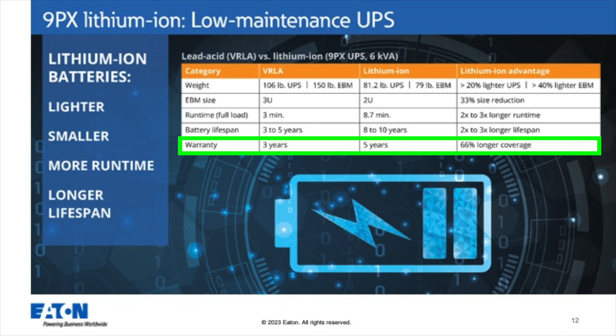Again, the set-and-forget-it message applies to battery lifespan: up to 10 years with the Lithium-ion UPS versus 3 to 5 years for VRLA. Depending on application, you may need a battery change at year 3.5 or 4, up to 5 years for the VRLA solution. And of course there's the warranty: 3 years coverage for the VRLA UPS versus 5 total for the Lithium-ion UPS.